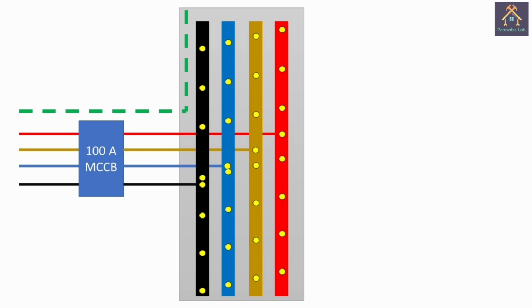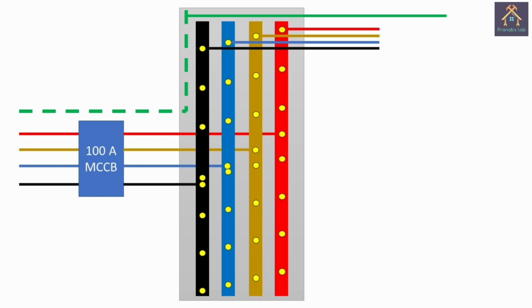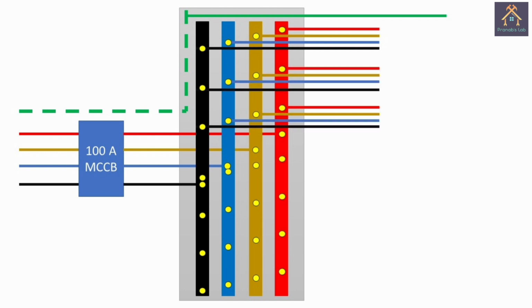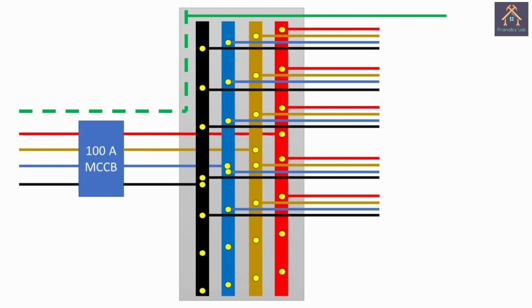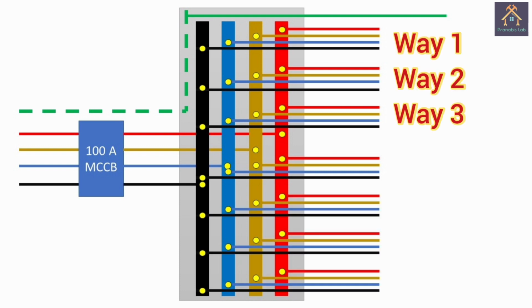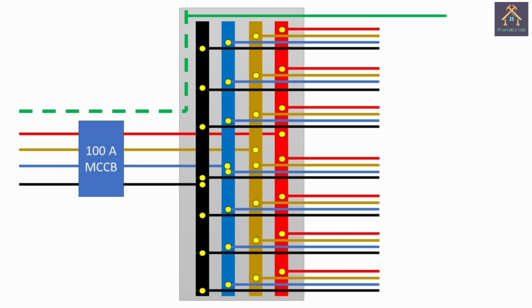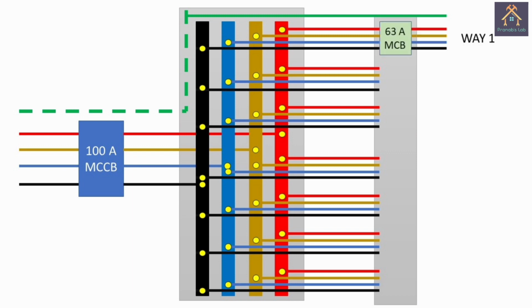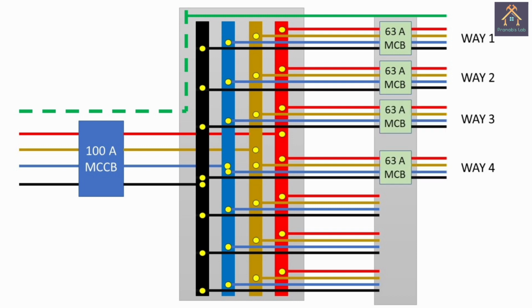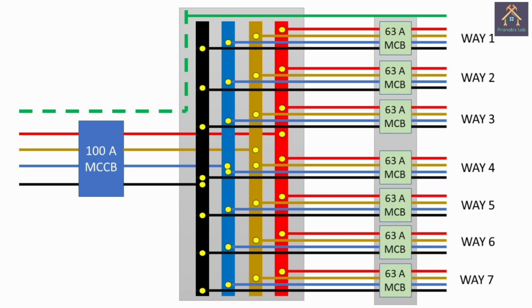You can see there are different tapping terminals marked on the busbar, and the earthing terminal is connected into the busbar chamber. Now you can see the different tappings are taken from the busbar. The set of cables that is taken out from the busbar is called a way. There are a total of 7 ways, and the 7-way cables are inserted into the MCB chamber. Each way is connected with a 63 ampere 4-pole MCB, so that we can easily control that way without disturbing the other ways. So that was the basic connection diagram of the panel.